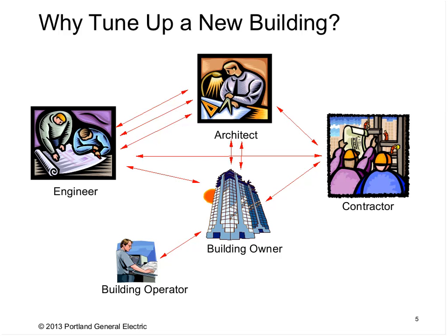The engineer may want to supply 55-degree air to the space, but maybe the contractor has put in different equipment, or the building operator wants to operate at a different set point. There may or may not be any coordination on how that would affect the operation of the building.